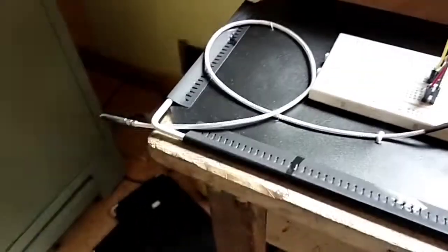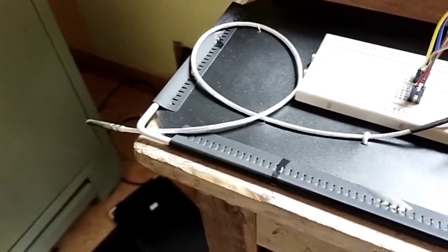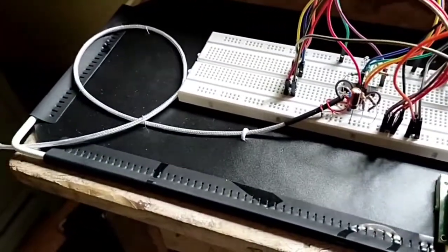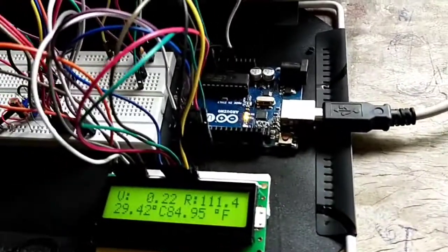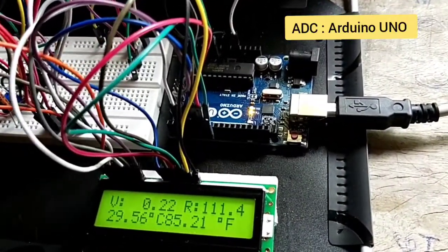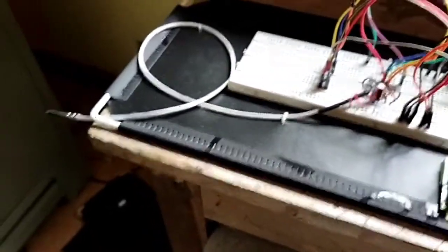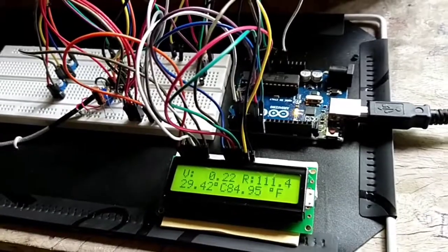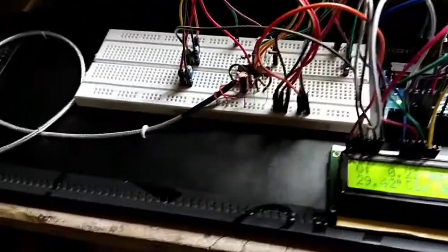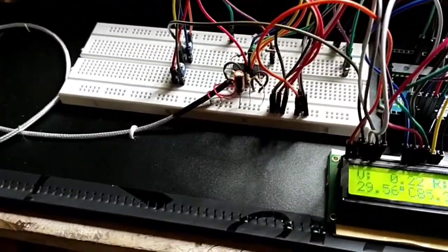One of the major problems with an RTD is that it generates an output in resistance or ohms, which cannot be directly interfaced into a circuit board or ADC board. Typically in industrial applications, an RTD sensor is interfaced with a PLC or DCS using RTD modules. In our case, I have designed an amplification circuit.